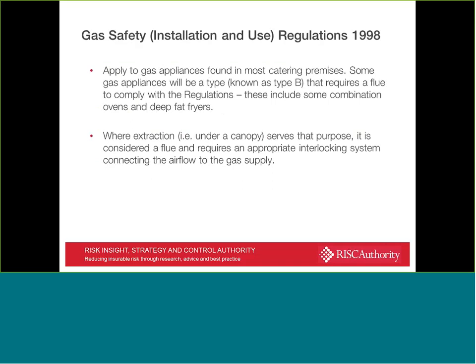There's also the Gas Safety (Installation and Use) Regulations, which apply to gas appliances that are found in most catering premises. Some appliances, you'll know, will be known as Type B, and these require the flue to comply with the regulations. Type B equipment is likely to include some combination ovens and deep fat fryers, and it indicates where extraction, i.e. under a canopy, serves that purpose, it is considered a flue, i.e. it's exhausting gas away, or could be exhausting gas away, and requires an appropriate interlocking system connecting the airflow to the gas supply. You don't see that in all catering establishments, certainly not in my experience.